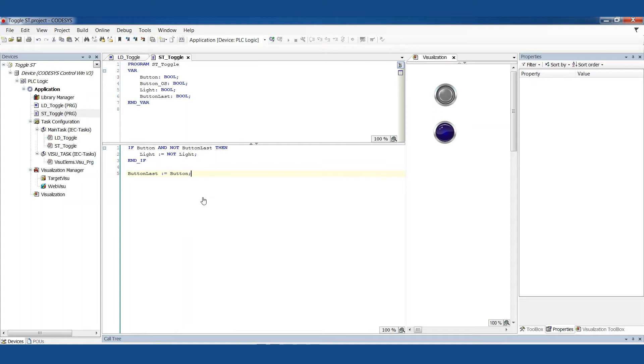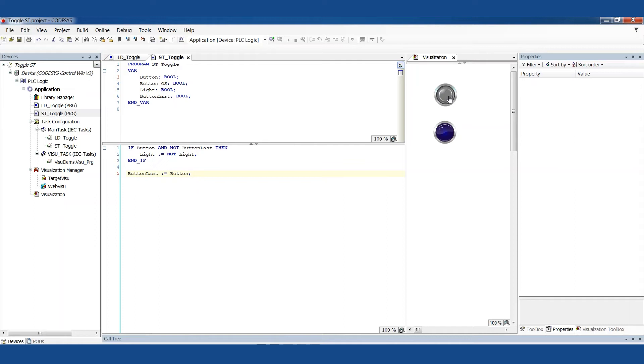You can't just say, whenever that's on, change the state of the thing. Instead, we're going to have to do what's called a rising edge detection. We're looking for that one rising edge as the signal of the button turns from off to on, zero to one, zero volts to 24 volts. When that contact closes, exactly at that moment, we want to detect that spot and not worry about before or after it. We're not just watching as I click this button, is it on? We're saying, is it on and was it not on last time I looked?